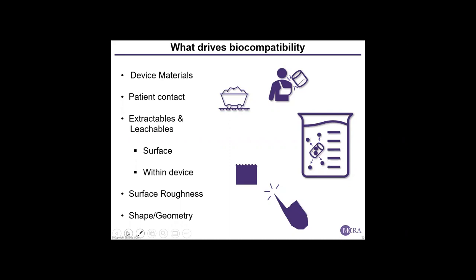And then similarly, shape and geometry can impact local tissue effects as well. So I've shown here, just for the sake of illustration, a shape of a potential medical device that has a protrusion and a sharp point. As might be intuitively obvious, if you were to implant this subcutaneously in a patient, you may have local tissue damage or irritation, and you may not have that same effect if you were to take the same materials but have a smoother, rounded surface. Again, pretty simple concept, but this is often overlooked in biocompatibility evaluations done by medical device manufacturers.